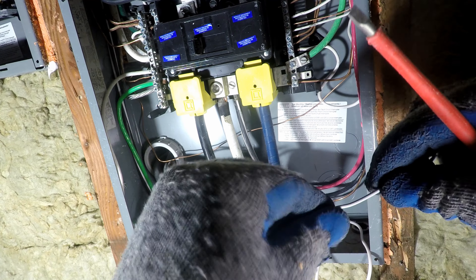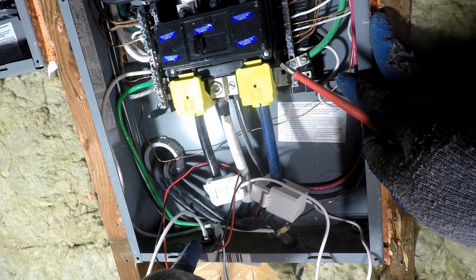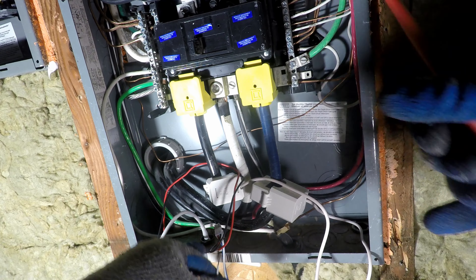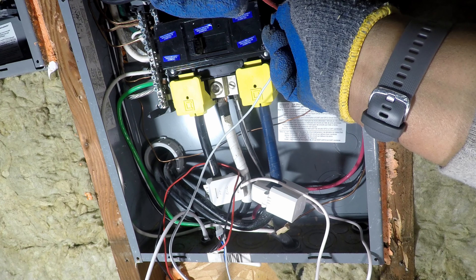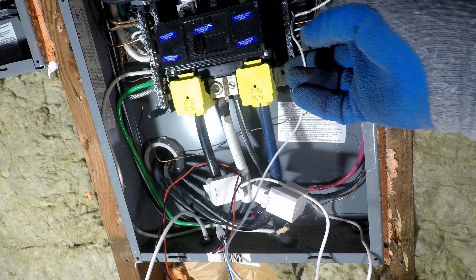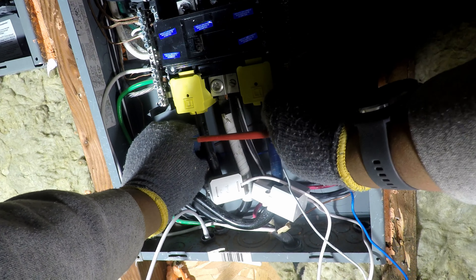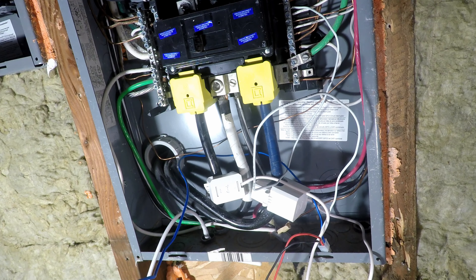The white insulated aluminum wire is installed on the shared bus. It is important that each screw on the bus secures no more than one wire. These wires are not as rigid as solid wires and take more effort. Twisting helps the wire not fray during installation into the shared bus — this feels like threading a needle. Throughout the install, Kofi was cognizant that the wires will easily become a mess, so routing them behind the service mains is a good option to keep them manageable.